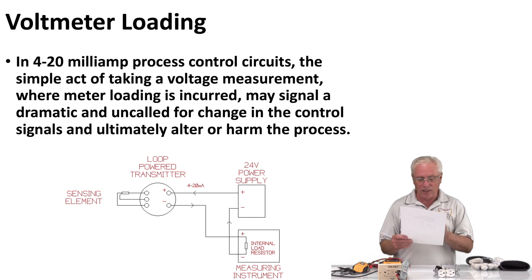On this slide, I wanted to talk about 4 to 20 milliamp process control circuits. The simple act of taking a voltage measurement where meter loading is incurred may signal a dramatic and uncalled for change in the control signals and ultimately alter or harm the process. I have an example of that. When I was instructing a class, we were trying to set up a lab for apprentices. We had a proximity sensor and a plate, and we wanted to make it so that as the plate moved closer, a light that was controlled by it got brighter and brighter. As we withdrew it, it dimmed.